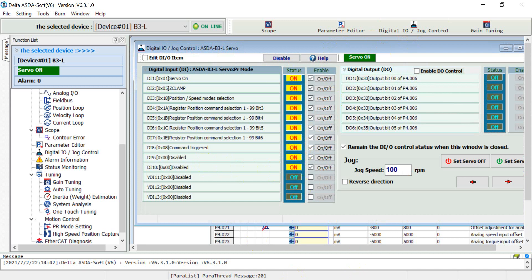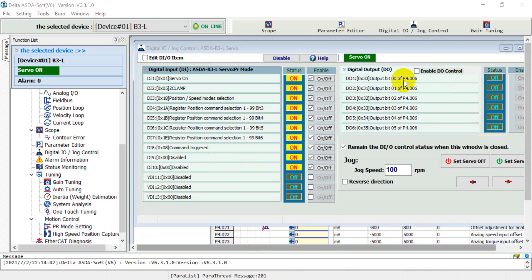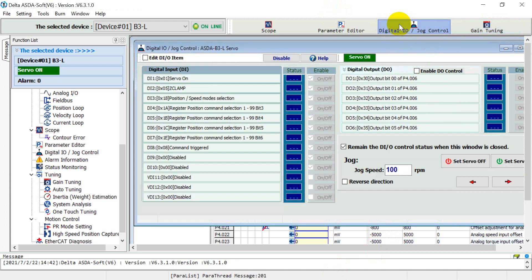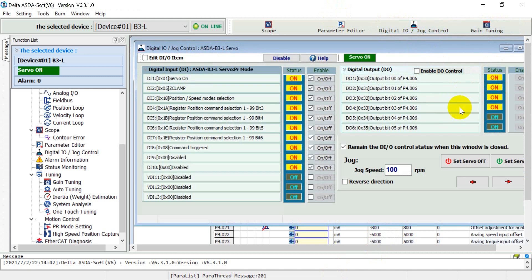So you can see now we already defined the parameters — the output bit is controlled by Modbus. Then we give the value in P4-006. We modify this value to 15, so that means DO1 to DO4 will be on.